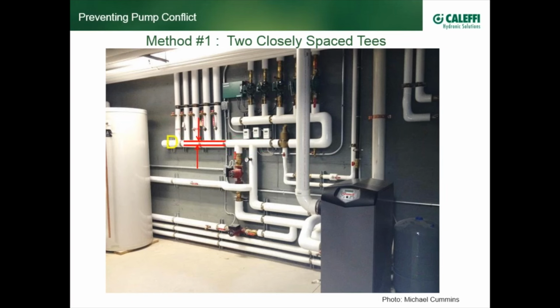It's important to follow this rule of thumb, though. If your supply return header over here on the secondary has a pipe diameter of D, your center to center spacing on your primary connections needs to be less than 4D. 3D is okay, 2D, the smaller the better. But once you get above 4D, for instance, if the contractor, rather than placing the pipe here, placed it here, now those pumps would see each other and begin back pressuring against one another.